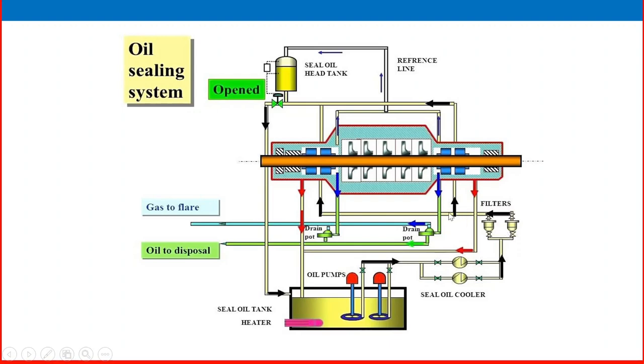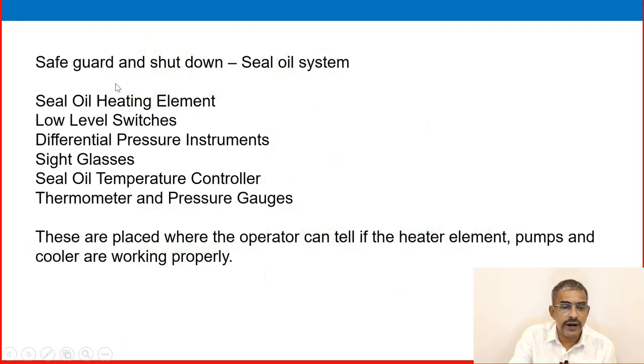The seal oil enters both sides of the sealing system on the shaft, then goes through cooling and returns to the seal oil tank or reservoir. Heaters are provided during winter to ensure sufficient oil flow and prevent the oil from becoming too viscous. Drain and other systems are also present. This completes the overview of the seal oil cooling system.